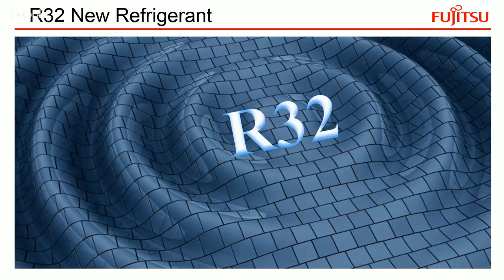R32 is the latest refrigerant to send shockwaves through our industry. I'm not sure if you know, but if you've been using 410A, R32 actually makes up 50% of 410A. And R32 is a single component refrigerant, making it nice and easy to use and recover.